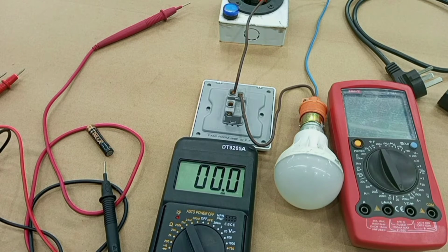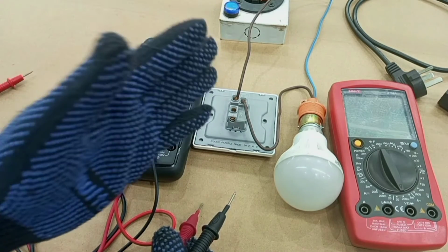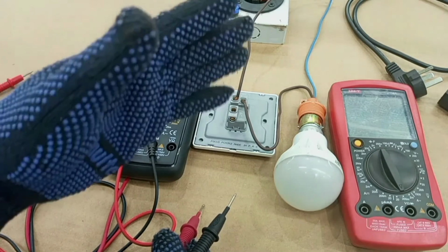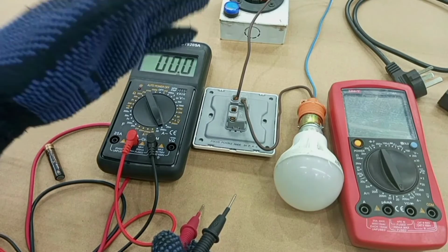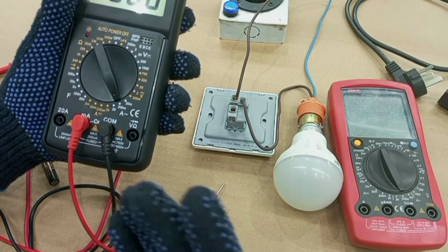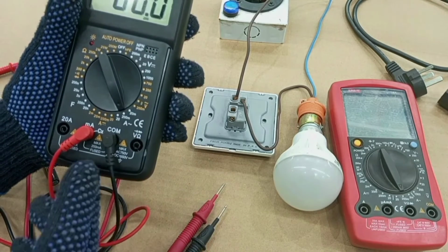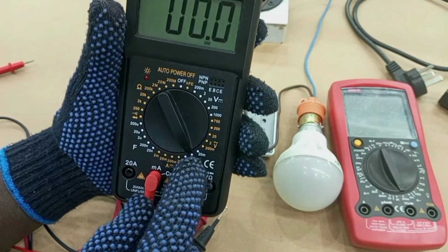We have done AC current. Now, when measuring DC current also, it is the same steps that are required, just that a DC current will be supplied from a DC source, which is usually from a battery. And so most of the time, for loads that are supplied from batteries, if the total current to the load is expected to be below 200 milliamp, then you set your probe to 200 milliamp, and then you set your dial to 200 milliamp. But this time, you would have to look for DC current, not AC current.